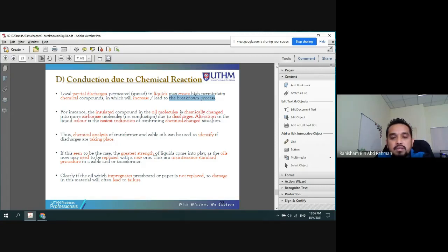The chemical formation within the material will develop further - for example, carbonized molecules will develop undesirable gases within the material, and also produce undesirable molecules that may have characteristics which trigger or facilitate current conduction within the insulator. That is the process that usually leads to the failure of the insulator.